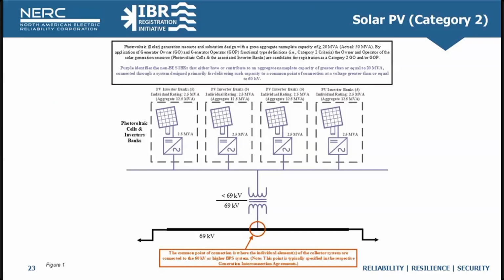This figure depicts a solar generation resource and substation design with an aggregate capacity of less or of greater than 20 MVA. Oh, I'm sorry. Hang on. I skipped over a diagram in my notes. Let me start over again. So this figure on slide 23 depicts a solar generation resource and substation design with an aggregate nameplate capacity of greater than or equal to 20 MVA. The generation resource consists of 20 inverters individually rated at 2.5 MVA for an aggregate nameplate capacity of 50 MVA, which exceeds the 20 MVA threshold.